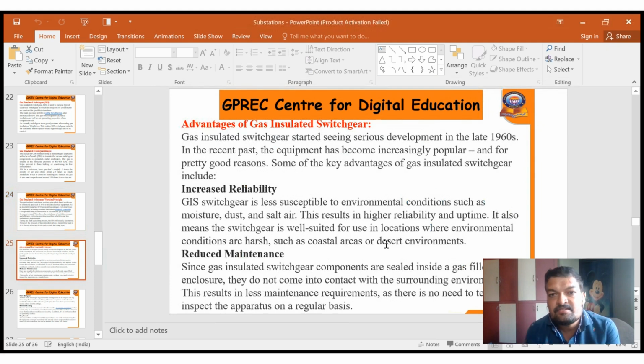So what are the advantages of gas insulated switchgear? Gas insulated switchgears have more advantages as compared to the air insulated substation. The main advantage is increased reliability. Gas insulated switchgear is less susceptible to environmental conditions such as moisture, dust, and salt air. Why? Because it is enclosed in an insulated vessel. Because of this enclosure, it does not come in contact with moisture, dust, and salt air. This results in high reliability, and that is a main advantage of the gas insulated substation.